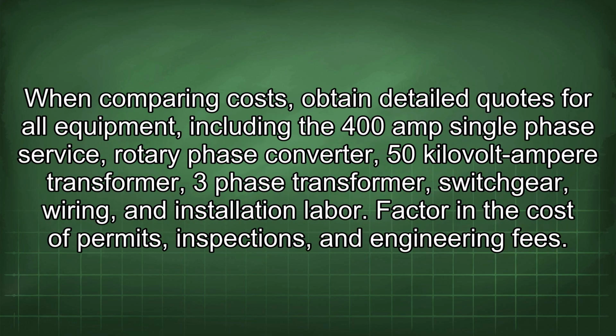When comparing costs, obtain detailed quotes for all equipment, including the 400 amp single-phase service, rotary phase converter, 50 kVA transformer, three-phase transformer, switchgear, wiring, and installation labor. Factor in the cost of permits, inspections, and engineering fees.